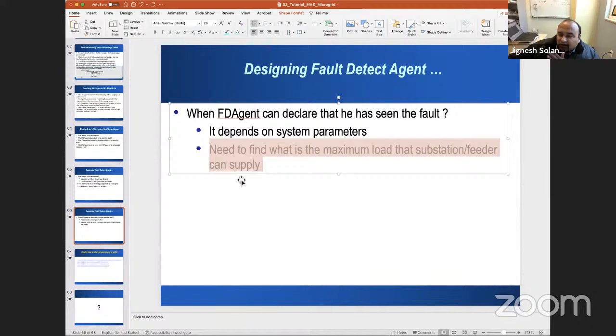For restoration, the agent has to find the other feeder agent and determine how much that agent can supply, similar to an earlier example. Are we closer to the fault? Are we overloading? If the answer is no, we can close the tie switch; if yes, we need to figure out how to handle that and what system design is needed.